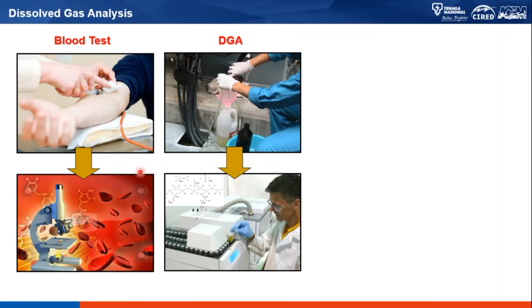example of when you take an oil sample out of a transformer and send it to the lab. So what we can analyze is the diseases, the symptoms that could affect the transformer based on the data that is available from the oil, based on this information that we can extract to know the incipient fault or the fault, if there is any inside of our transformer. Because of that, DGA, dissolved gas analysis, has actually gained worldwide acceptance as a method for the detection of incipient faults inside of transformers.